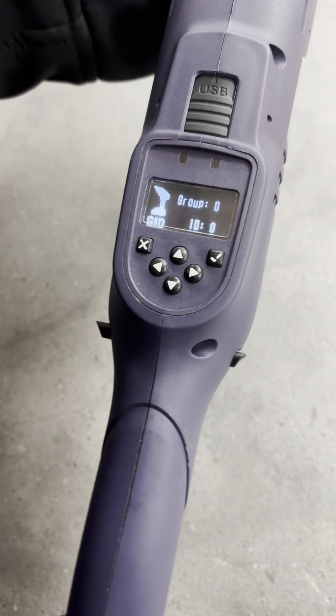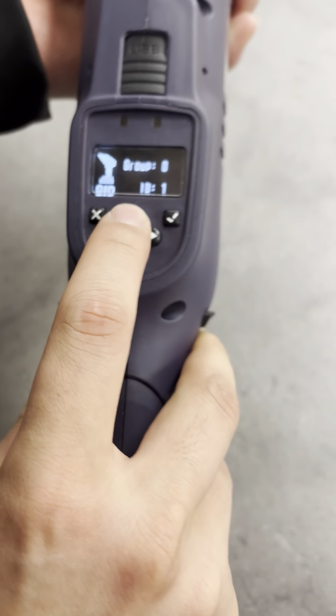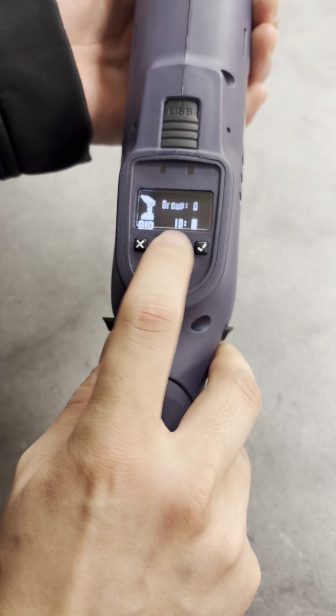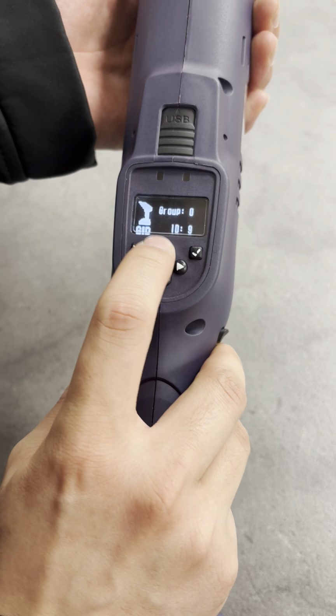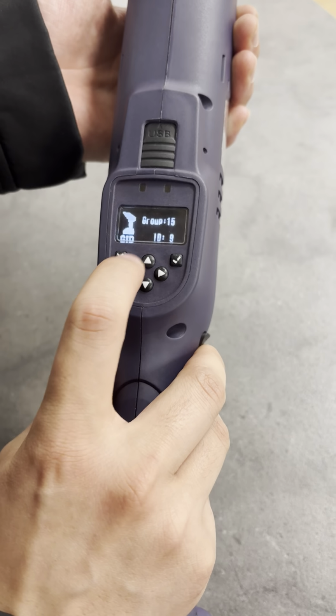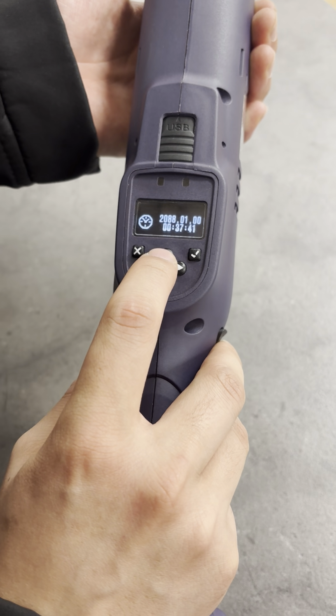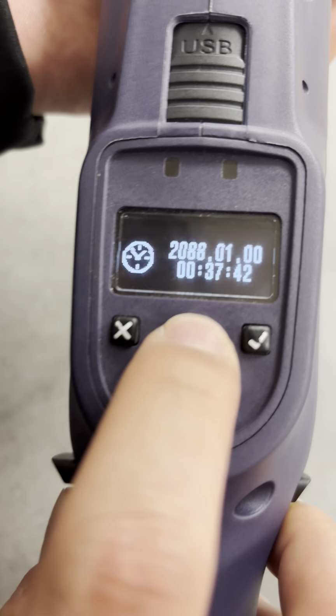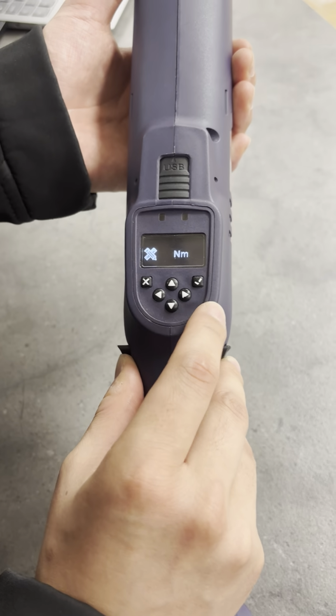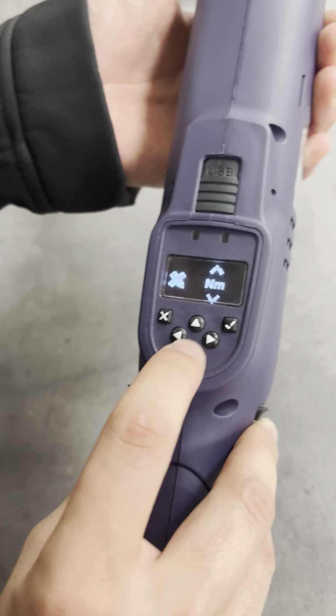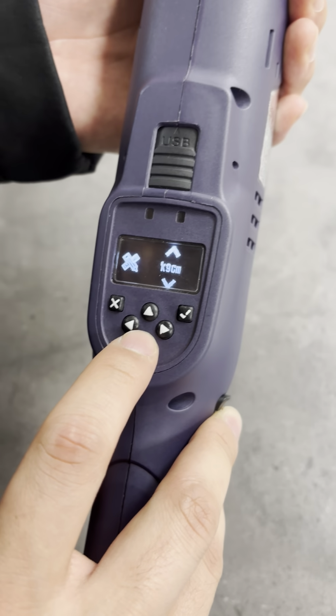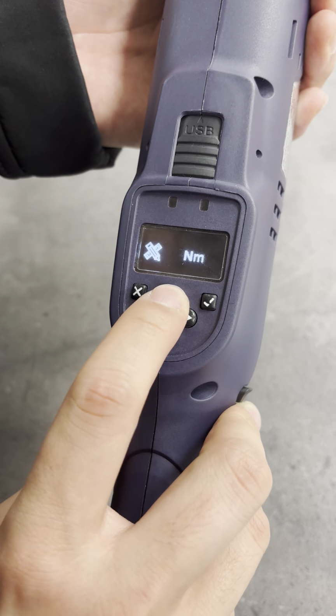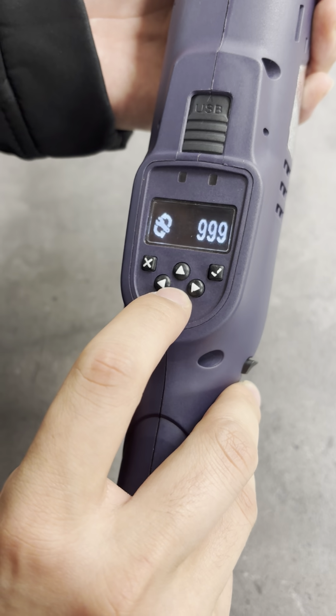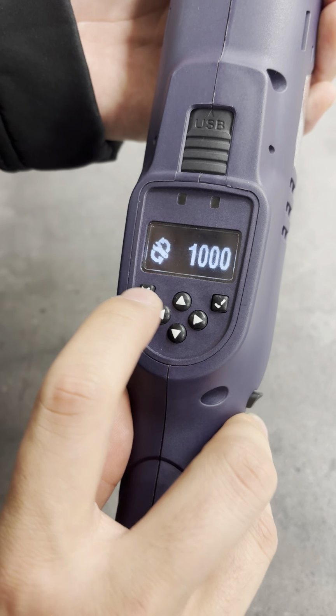Now this is the grouping ID. So this is very important when you're connected to our software. Obviously the tools, you can have up to 9 IDs, and I believe 15 different groups. This is where you set your date and time. This page is where you set the units for your torque. So I can have Newton meters, foot pounds, inch pounds, kilogram centimeters, back to Newton meters. This is how you set your cycle count. So this is a maximum of 1,000 all the way down to 1.